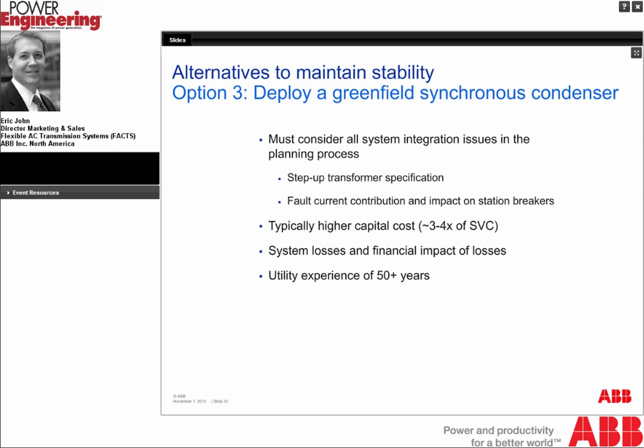The second is that the Greenfield synchronous condenser is going to make a fault current contribution. And again, this can have benefits in the system from a system stability point of view, but it can also have an impact on station breakers. And this is a nuanced difference from the conversion, because in the case of the conversion, you already have a generator that would be contributing fault current. In the case of a Greenfield, you might be moving it to a different station, and you need to consider what the impact on the station breakers is of that incremental contribution of fault current.